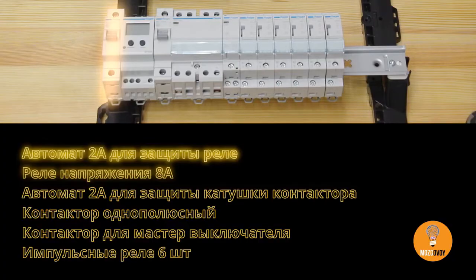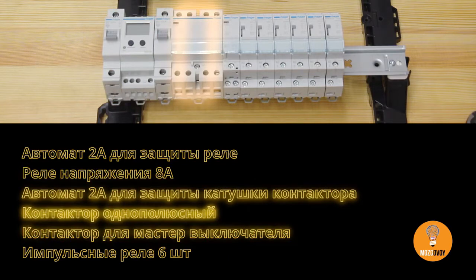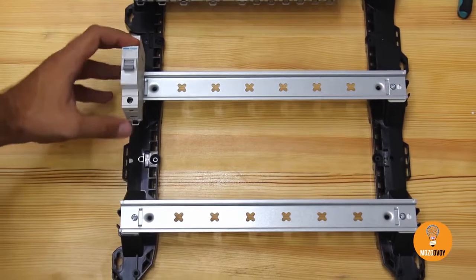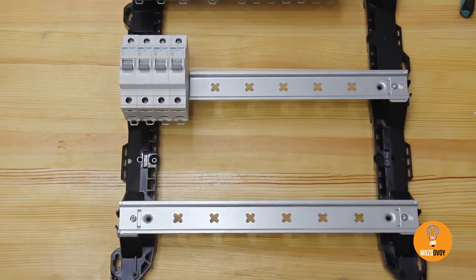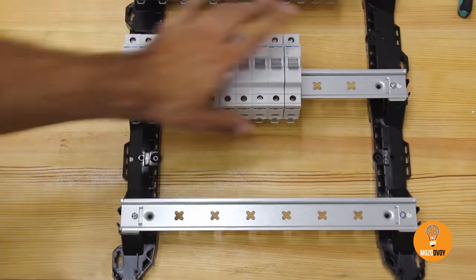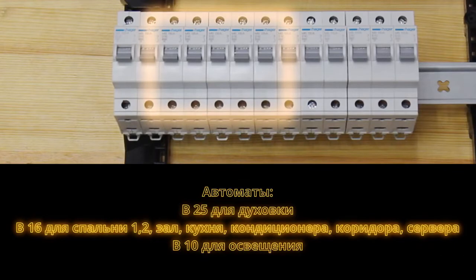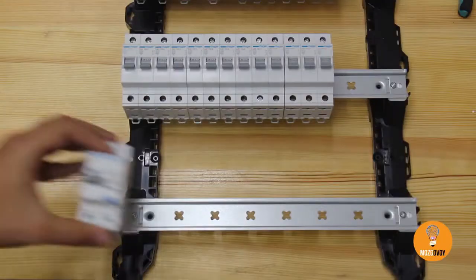I'll create a separate video with more details on how to handle contactors, how to wire them up, and how an impulse relay works — we'll assemble a prototype to demonstrate all the processes. B25 goes for the oven, B16 for bedroom 1, bedroom 2, living room, kitchen, air conditioner, hallway, one for display, one for the server, 5 MCBs for the lighting at B10, and differential breakers.